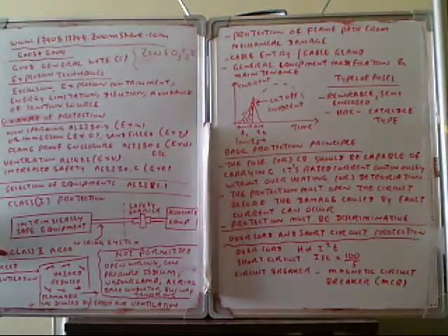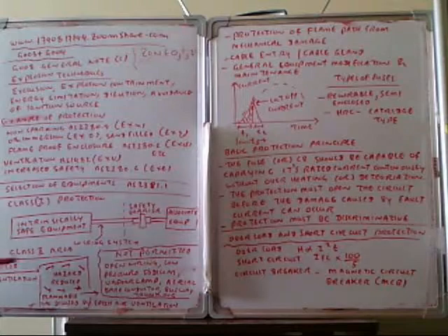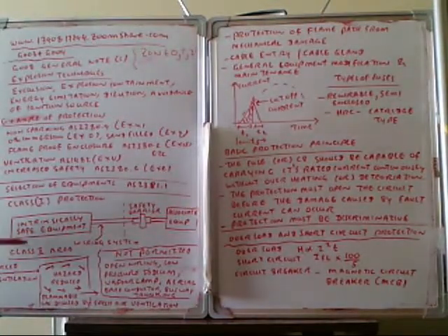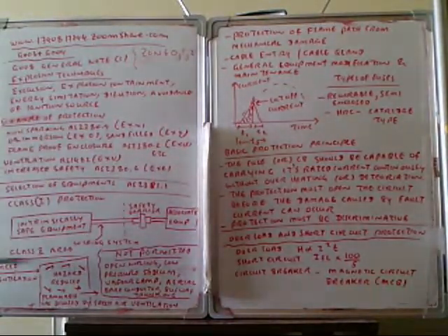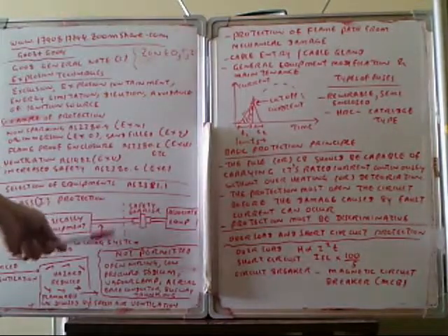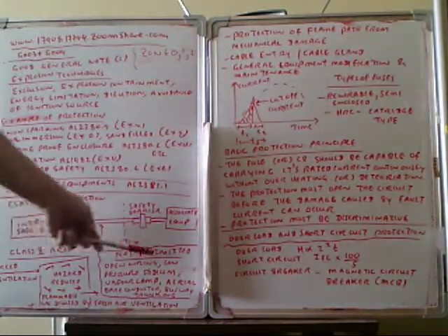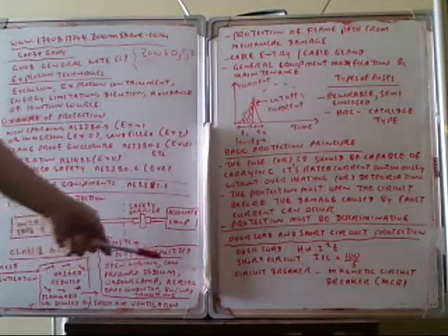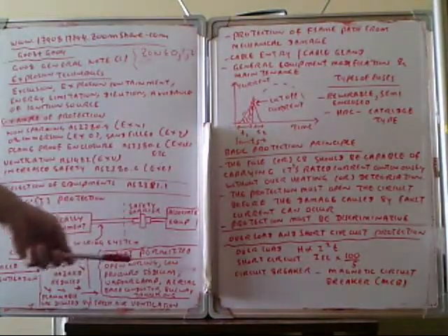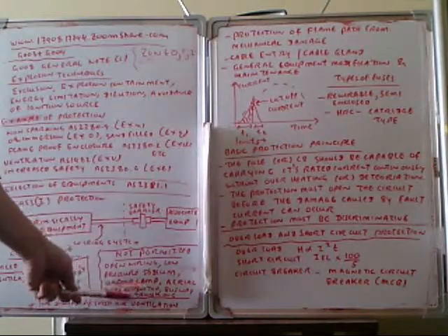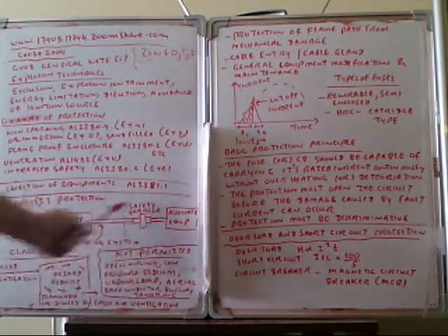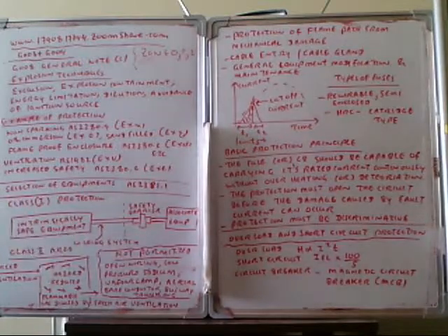In the meantime, class 1 area: the explosive gas needs to be ventilated, so forced ventilation is put into the system. The flammable gas is diluted by fresh air or ventilation. In the hazardous area, some systems are not permitted. We don't permit open wiring, low pressure sodium, busway, and trunking systems. Those systems are totally not permitted in the hazardous area.